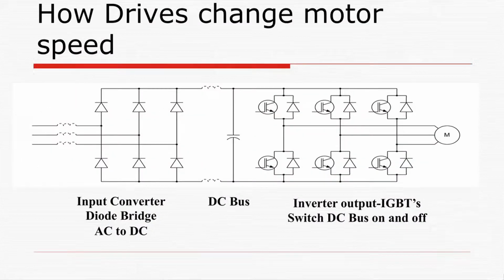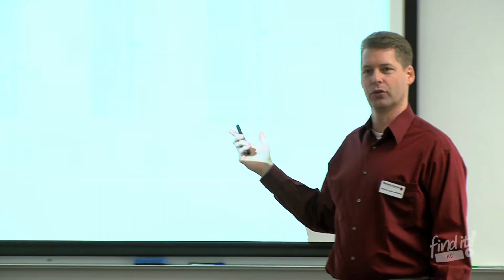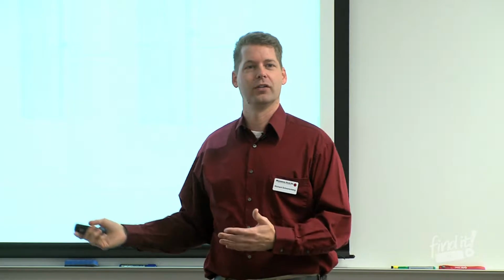All right, so what is a variable frequency drive? They're these magic black boxes, right? Or in this case, magic white boxes that sit on the wall. They hook between the three-phase power coming in and the three-phase out to the motor. All variable frequency drives run three-phase motors. They can run on three-phase power coming in nominally, but they could also run on single-phase power. And Paul's going to talk about some single-phase issues that are coming up soon too.